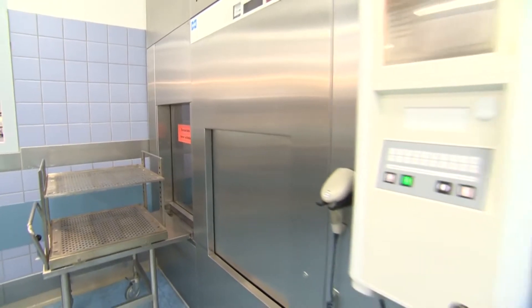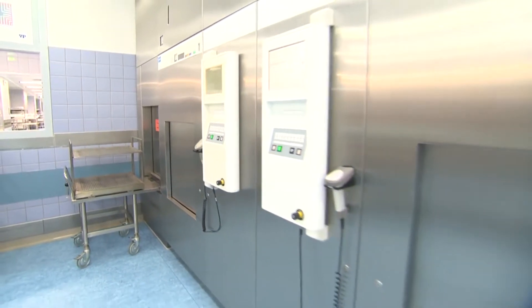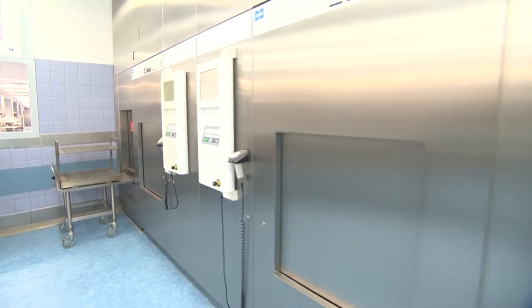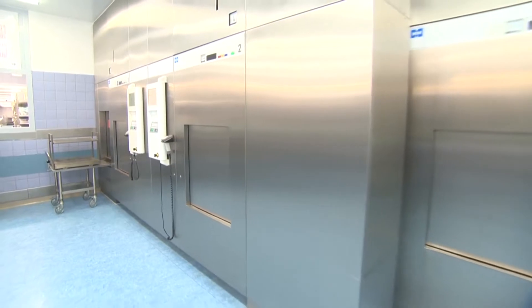At the end of the preparation process is sterilization. Steam sterilization remains, as before, the most effective method of freeing heat-resistant instruments from germs which are capable of survival, leaving no residues or irreversibly inactivating them.